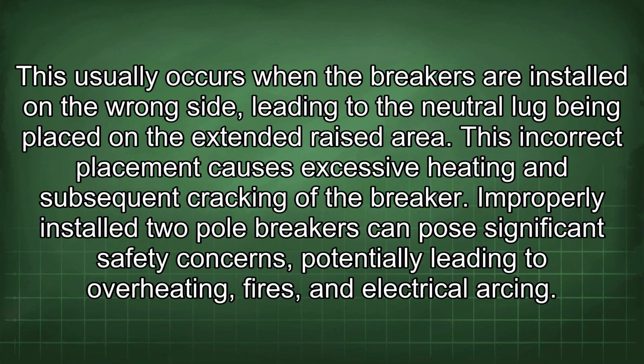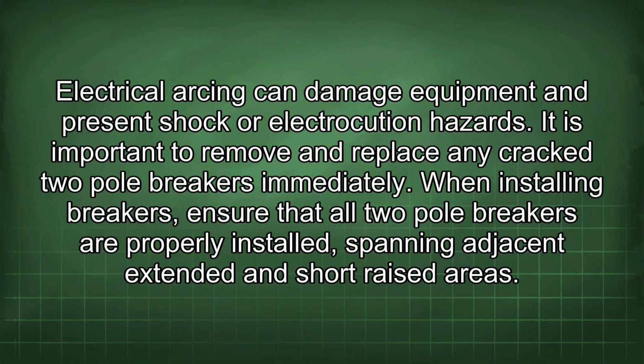Improperly installed two-pole breakers can pose significant safety concerns, potentially leading to overheating, fires, and electrical arcing. Electrical arcing can damage equipment and present shock or electrocution hazards. It is important to remove and replace any cracked two-pole breakers immediately. When installing breakers, ensure that all two-pole breakers are properly installed, spanning adjacent extended and short raised areas.